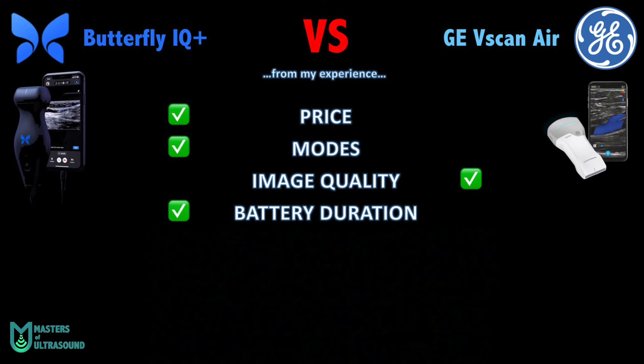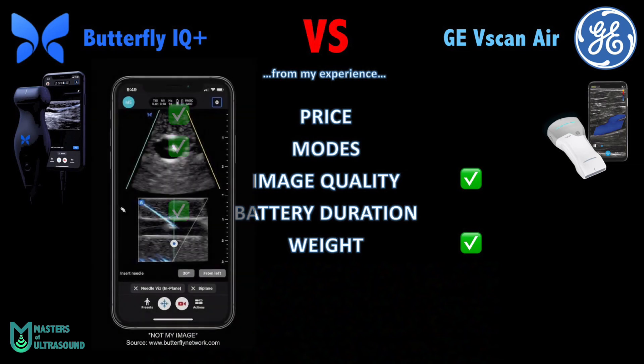If image quality is relevant for your use case, the Vscan Air may be the better choice. On battery, the Butterfly IQ has better battery duration in both exam time and total battery life, although the Vscan can recharge fully in under an hour while the Butterfly IQ lasts two to three hours. On weight, the Vscan Air wins — it weighs two-thirds of the Butterfly IQ and is easier to carry. It is also wireless with a smaller footprint, which may be useful for interventional procedures.